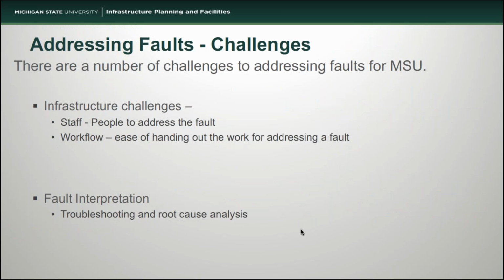We also have some challenges here at MSU in addressing our faults. Our primary one is an infrastructure challenge. With a large number of faults, you need to have staff that are able to address the faults. That's everybody from the people who are receiving the faults from the system via notification dashboards, to the control staff who look into the programming of the system and the set points to determine whether or not this is an issue with a sequence of operation and how the air handler should run, to tradespeople who, if we determine it's not a software issue, go out there and turn the wrenches and screwdrivers in order to figure out what the problem is and fix it.